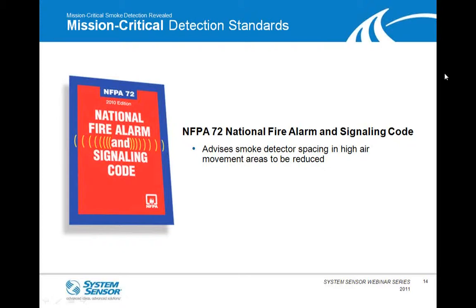This code, obviously I think everyone in the fire industry is fairly familiar with it. Basically, the only thing that kind of crosses over into that aspiration area, as well as mission critical, is where it advises smoke detection spacing in high air movement areas to be reduced. So you think about these mission critical facilities that maybe have hot aisles and cold aisles, high rates of air change in telecommunication, IT kind of areas. NFPA 72 is just saying, if you have these kind of high rates of air change, you do need to reduce the coverage or reduce the spacing of a standard smoke detector.